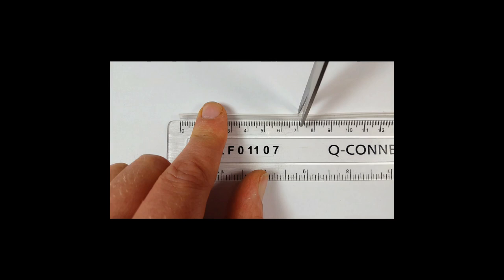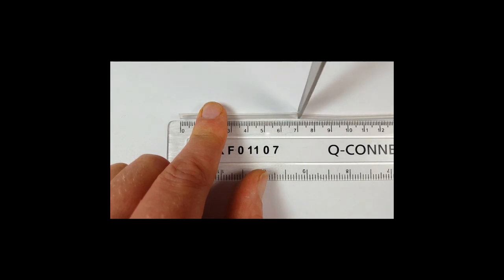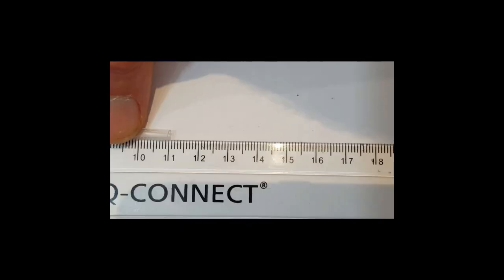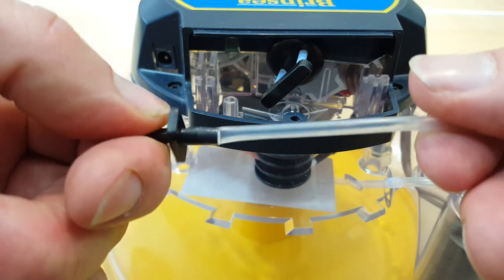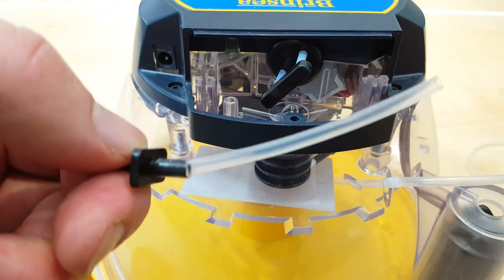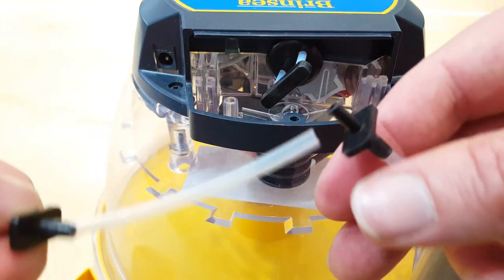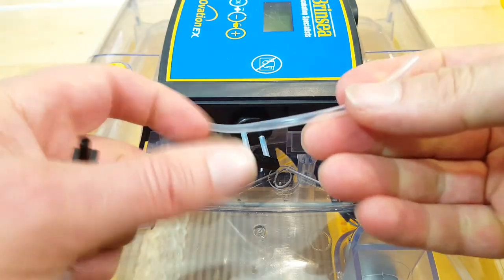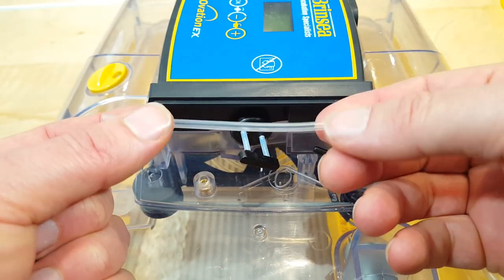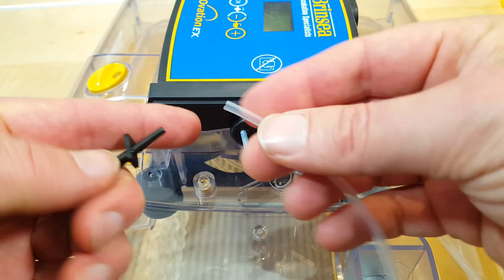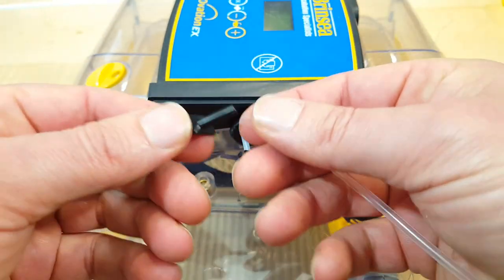Use a ruler and cut precisely to the right length with a pair of scissors. Remember you need 70mm for the Mini EX and Maxi EX and you need 110mm of tubing for the Ovation 28 EX and the Ovation 56 EX.